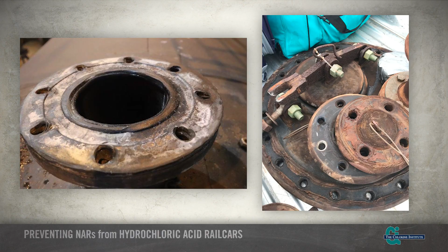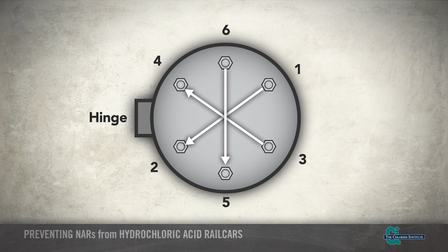Once all fasteners and gaskets are in good condition, all fasteners on fittings should be tightened using the proper crisscross pattern torquing method. Sample torquing patterns are shown here for fittings with 6, 8, or 10 bolts, but the concept is similar for fittings with a different number of fasteners. All fasteners should be tightened so they remain secured under normal conditions through the entire duration of shipment.